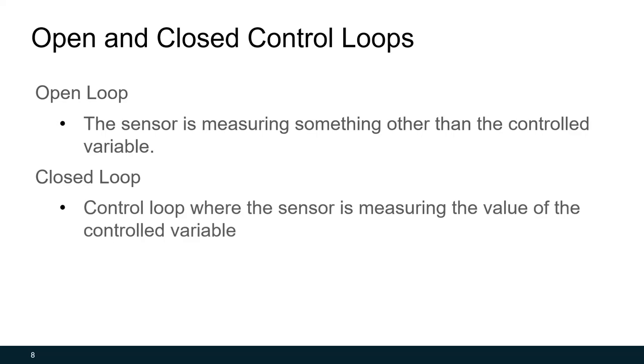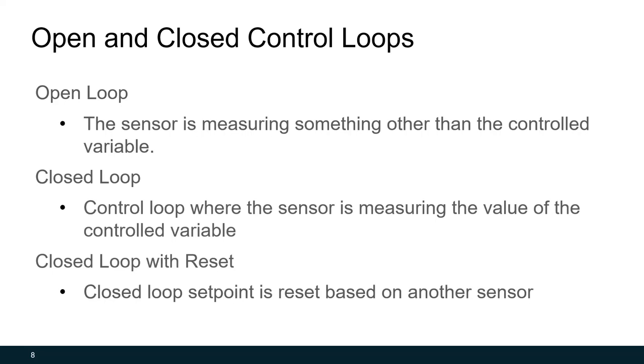There are two main types of control loops: an open loop and a closed loop. In an open loop, the sensor is measuring something other than the controlled variable. In a closed loop, the sensor is measuring the controlled variable directly. We can actually combine these to make a loop called a closed loop with reset, where the closed loop set point is reset based on another sensor.